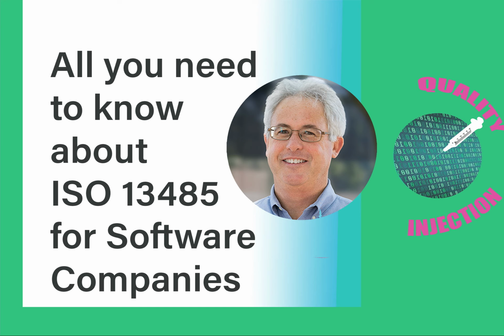So yes and no. There's a quality management system that's globally recognized, or a set of standards called ISO 13485. I'm based in the United States, so we also have the FDA. And so in lockstep with 13485 is 21 CFR 820, which talks about design controls. And really, I think design controls in the FDA world is the topmost regulation. But 13485 implements that. ISO 13485 is a quality management system that provides you guidance on how to document purchasing, how to document manufacturing, how to document design of your software, verification, validation, when you transfer it from design to manufacturing.